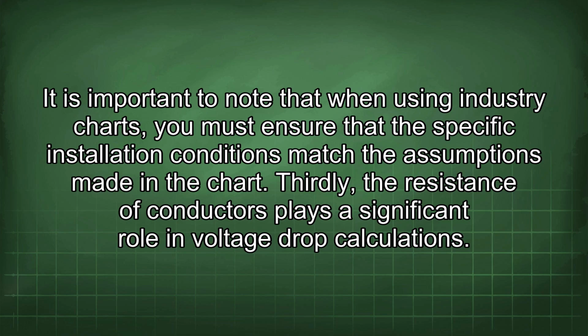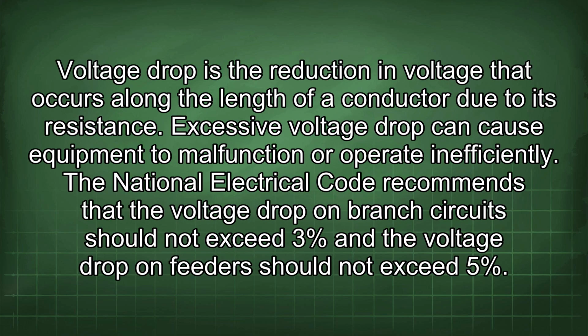Thirdly, the resistance of conductors plays a significant role in voltage drop calculations. Voltage drop is the reduction in voltage that occurs along the length of a conductor due to its resistance. Excessive voltage drop can cause equipment to malfunction or operate inefficiently. The National Electrical Code recommends that the voltage drop on branch circuits should not exceed 3% and the voltage drop on feeders should not exceed 5%.